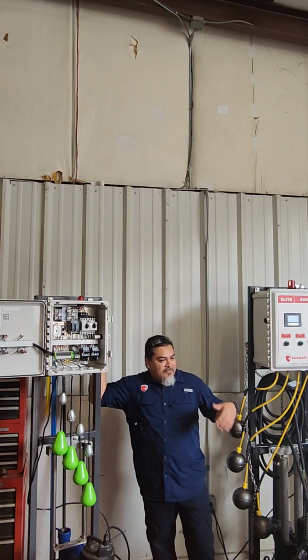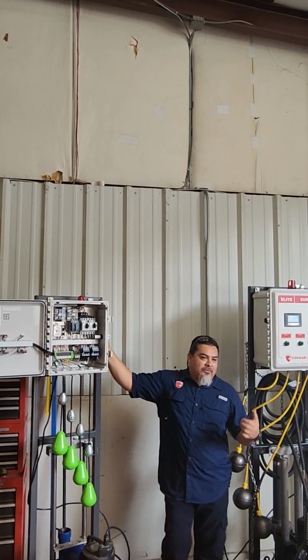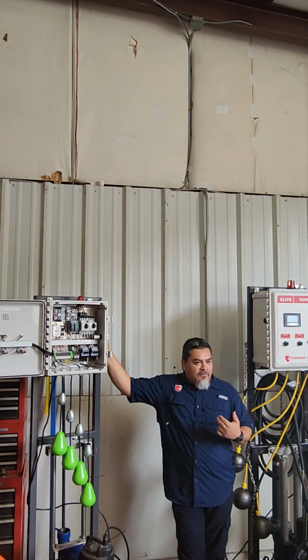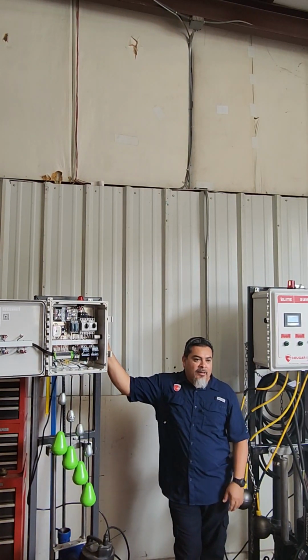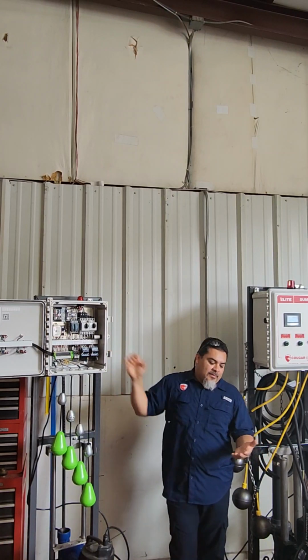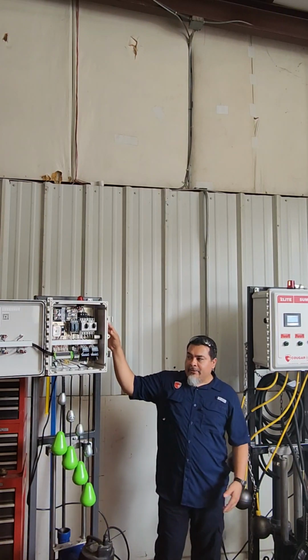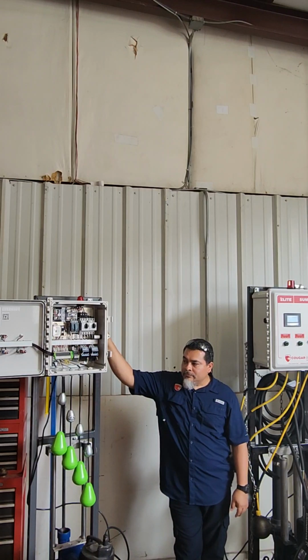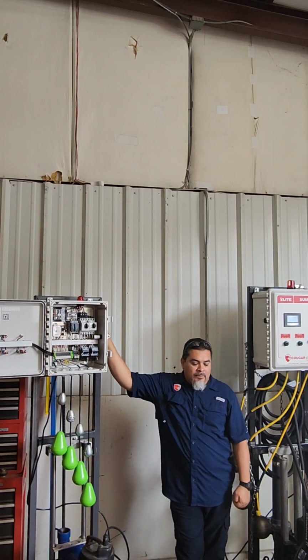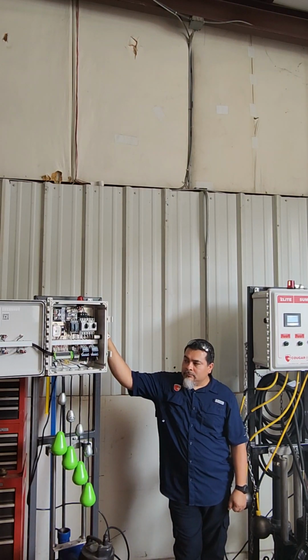So yeah, like I said, you stick it in there, you check your amperage, it runs low amperage, but you hear the pump running, but no water's flowing, it's many times airlock. Or the check valve is clogged up, it's not open. So if it's under amps, it means the pump's spinning freely, but it's not moving water. So either it's got air or there's something clogged downstream.